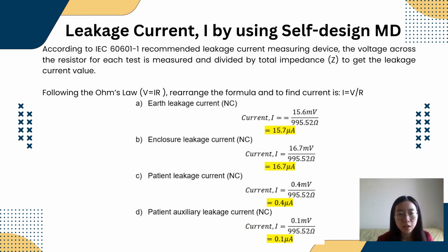So moving on to the next step, how do we calculate leakage current I by using the self-designed measuring device? According to this IEC recommended LC measuring device, the voltage across the resistor for each test is measured and divided by the total impedance Z to get the leakage current value.